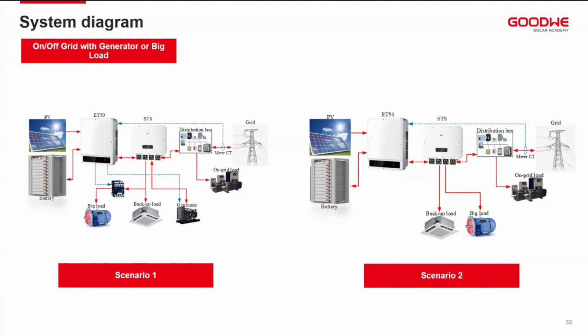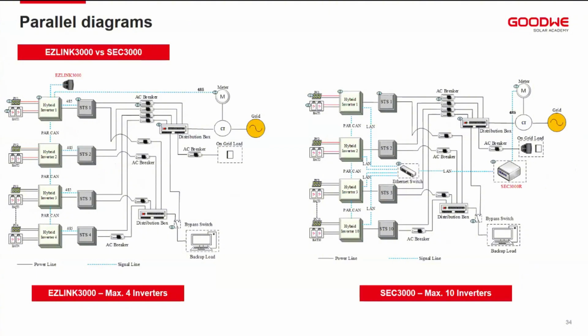Now, the big load operating can still be achieved using the smart way automatically. It can be disconnected during certain points so that only the backup loads can discharge the remaining charge on the batteries to the very low levels. Once the battery runs out, but because the client is not prioritizing on the diesel generator, you can include a manual changeover so that the generator now kicks in to supply the remaining loads or all of the loads, that is. So scenario two is for achieving that particular operating principle.